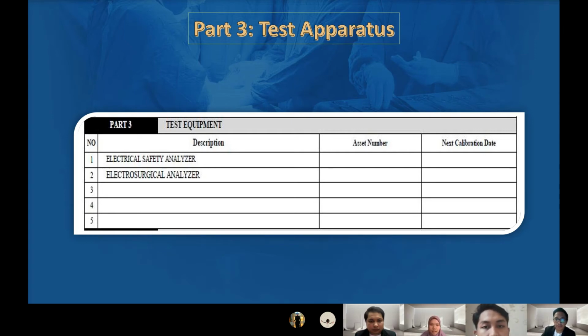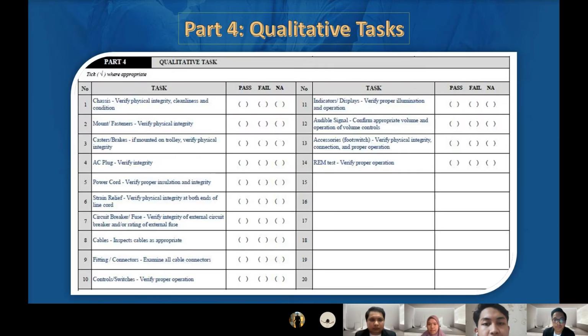Next is part 4, qualitative tasks. For tasks 1 until 14, we have to check and then decide whether the device is pass, fail, or NA (not available). First, the casing—check whether the external ESU casing is damaged or broken, and tick pass or fail.